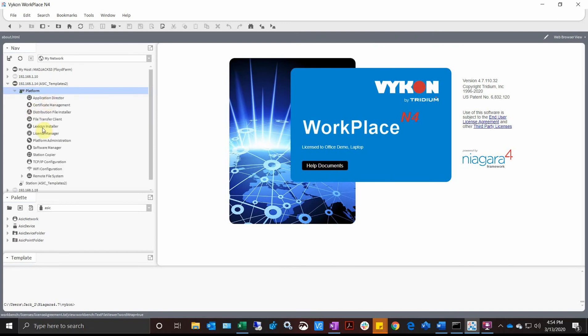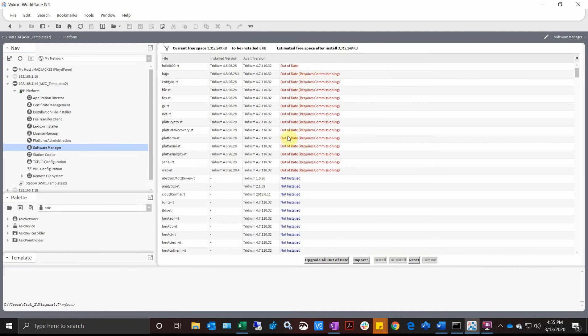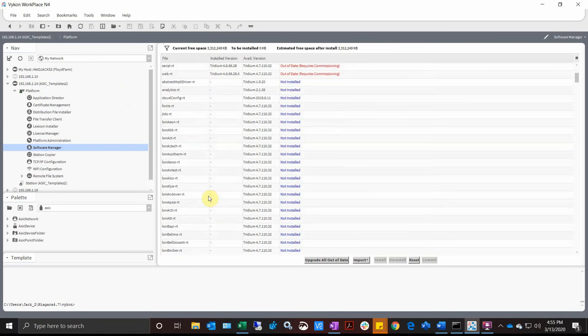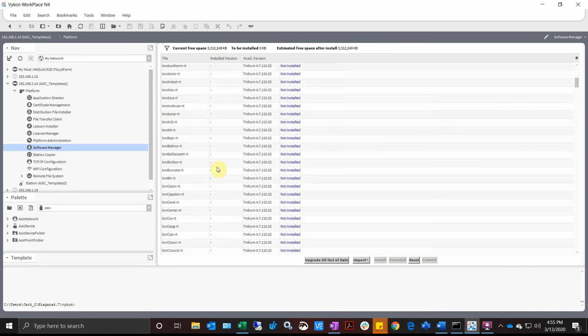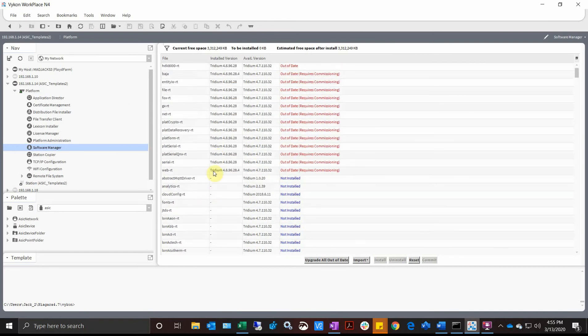All I'm going to do is expand my platform connection here and go to my software manager. You notice that it automatically tells you right at the top: out of date, out of date. What we're going to do is say Upgrade All Out of Date. This will get all your modules. This is just the core software because that's all I've got installed on this JACE right now, but if you have the BACnet module installed it'll be in this list too.